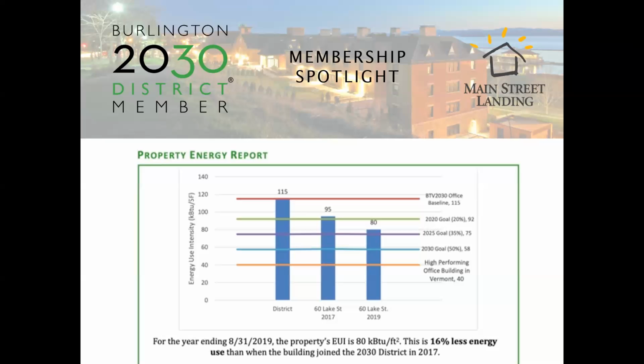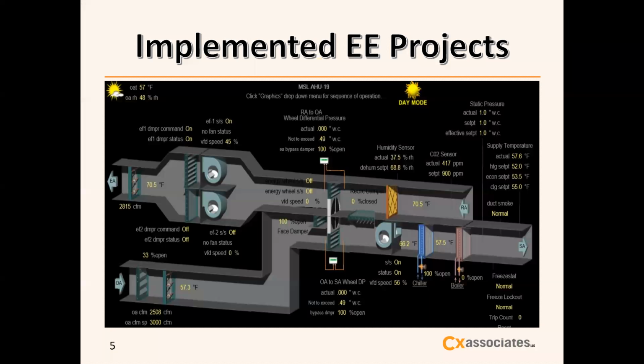So next, I'd like to dive into how we attained this 16% energy reduction between 2017 and 2019. In 2018, we went through a retro commissioning project where we implemented a number of measures. We upgraded the building automation system, which improved equipment controls as well as equipment operation oversight. We optimized the central plant control sequences. We installed LED lighting, and we modified the common area and event spaces mechanical systems schedules and set points.